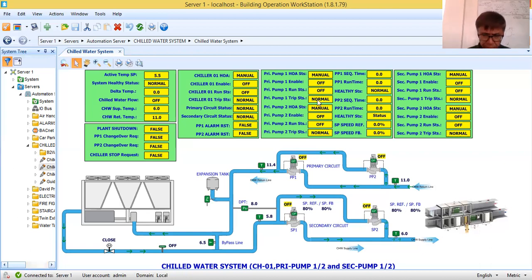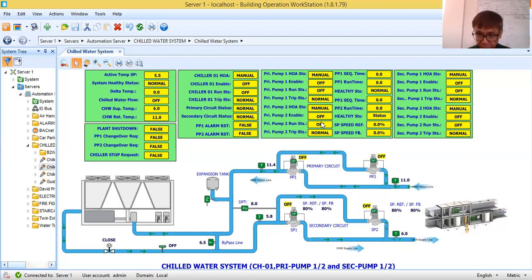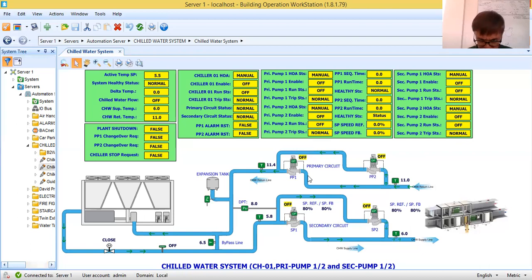The other component of the chiller system is the primary pumps. We have a primary circuit composed of two chiller pumps, also called primary pumps. The points being monitored in the primary pumps are: hand/off/auto, run, and trip. These are the basic monitoring points for a pump. We also have water flow monitored via a differential pressure switch across the pump.